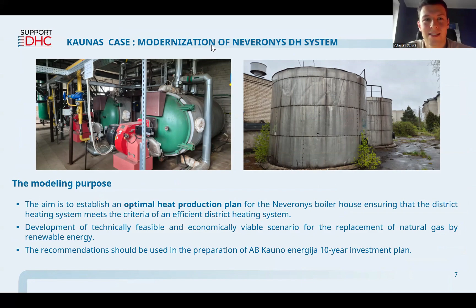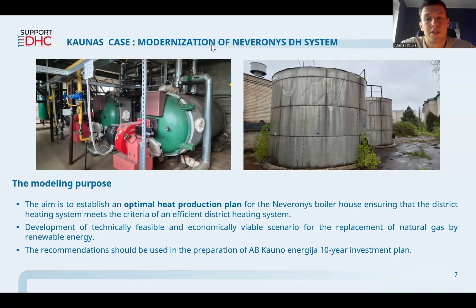Yes, okay. First of all, I would like to introduce everyone to the Kaunas district heating system, and specifically Neveronys, which has 3 main natural gas boilers covering the heat demand annually. The modeling purpose was to establish an optimal heat production plan, ensuring this district heating system would meet the criteria of an efficient district heating system, reaching 90% renewables in the existing district boiler house, by developing feasible and economically viable scenarios for the replacement of natural gas. These recommendations should be used for the future 10-year investment plan for the Kaunas district heating company.